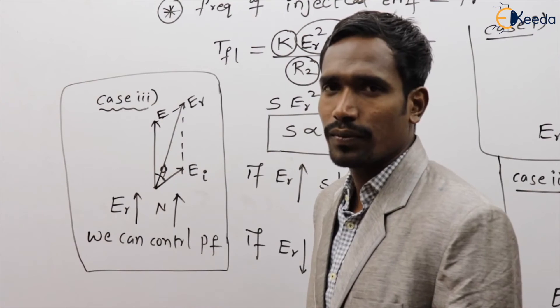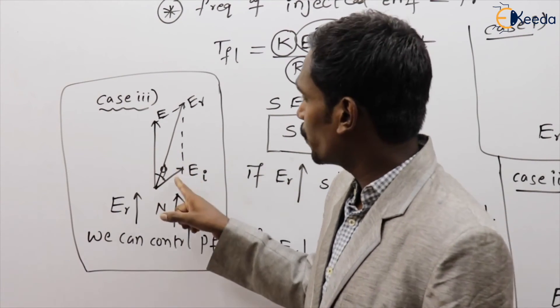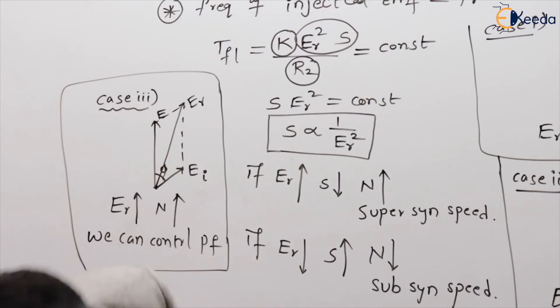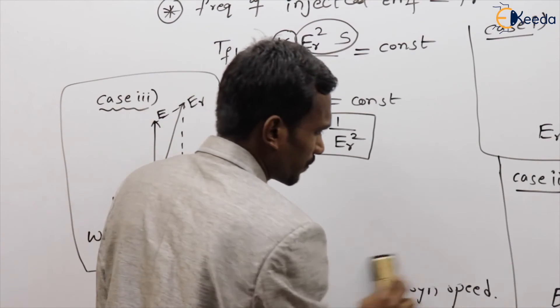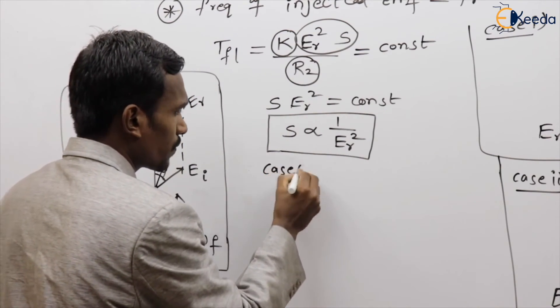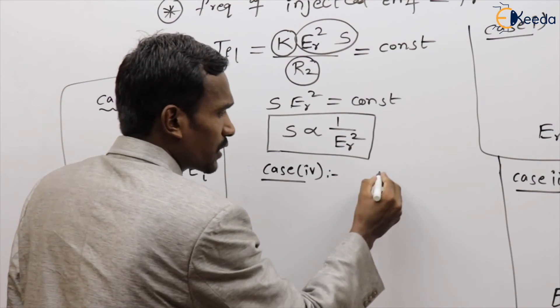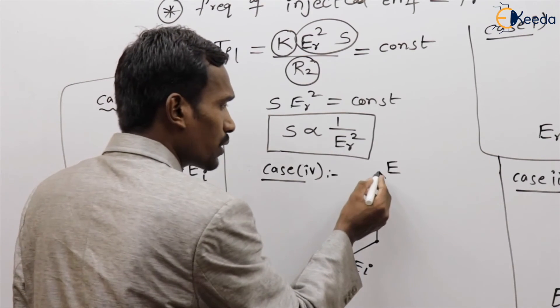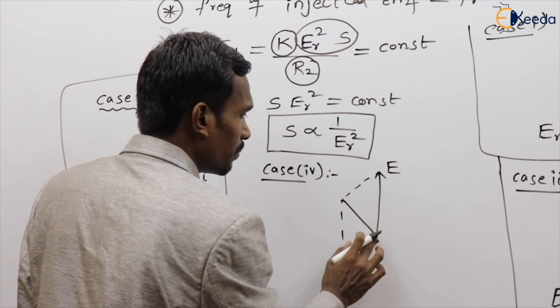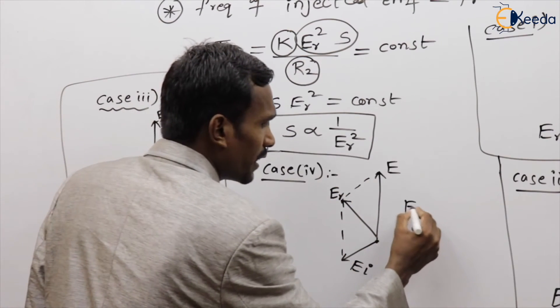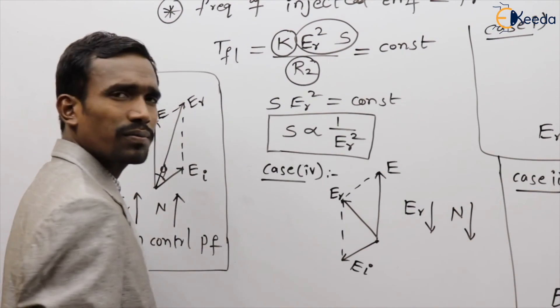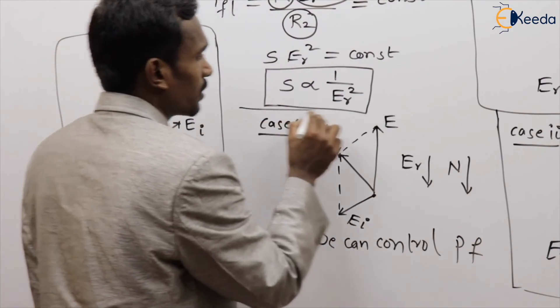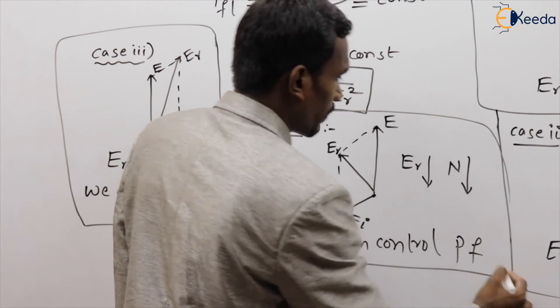Case four: the EMF is injected into the rotor out of phase with some angle. The resultant EMF reduces, and therefore speed also reduces. However, here too we can control the power factor — this is a key advantage of injecting EMF at an angle.